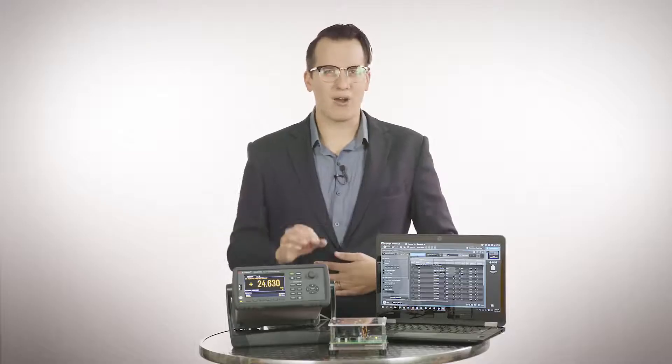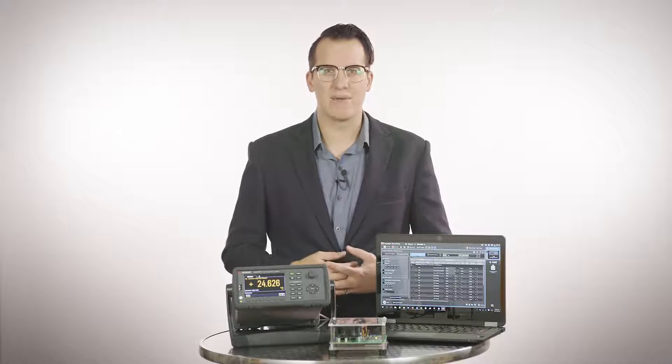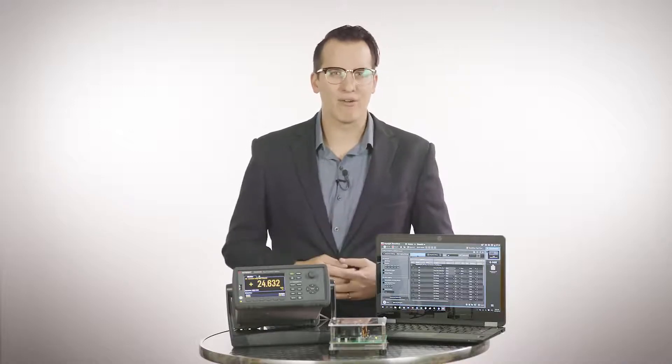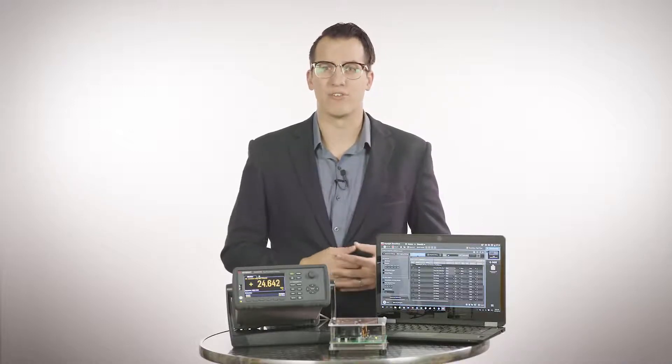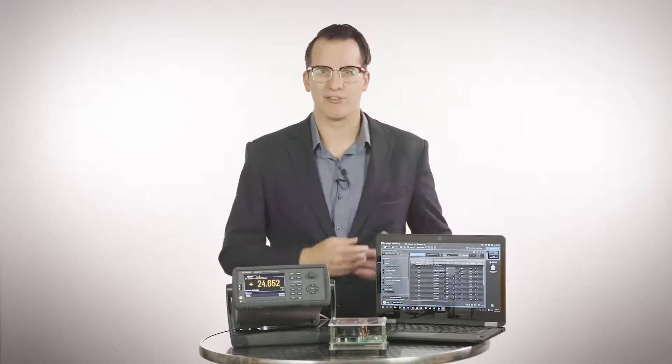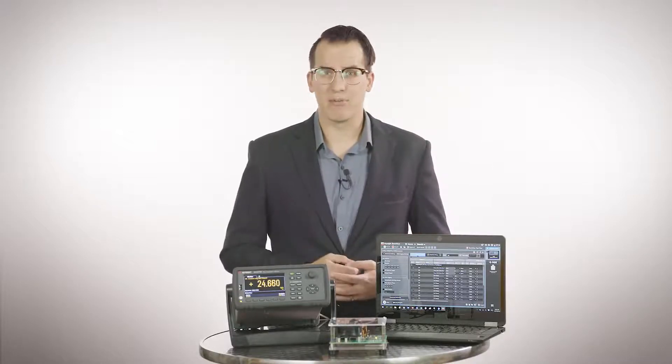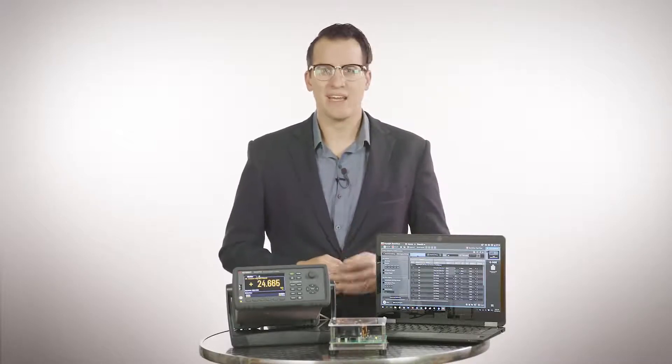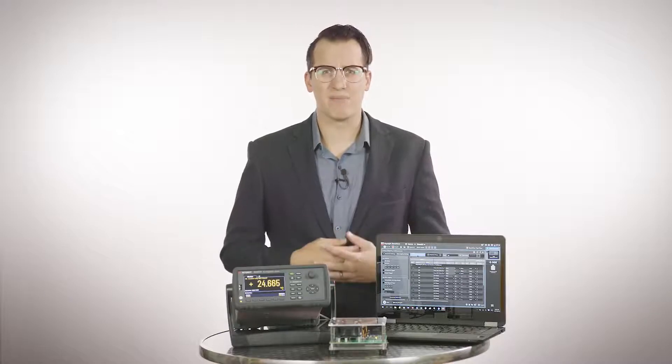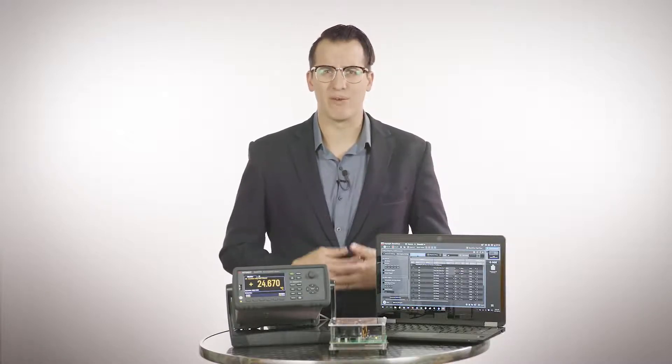It comes with a new auto calibration feature which compensates the internal DMM and the new DAQM907A multifunction module for drifts caused by time and temperature changes. It has 2x deeper memory, up to a hundred thousand readings. And this is non-volatile memory, which means it will still hold data when power is removed.